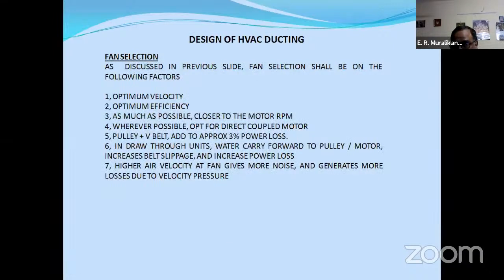Now, again, I discussed the fan optimum velocity, optimum efficiency, as close to motor RPM as possible, wherever possible, opt for direct coupled motor. See, plug fans also you can consider if the fan RPM is close to the plug fan RPM for the rated capacity.